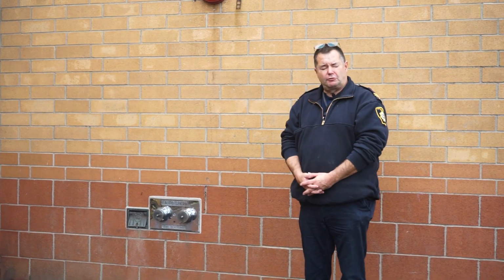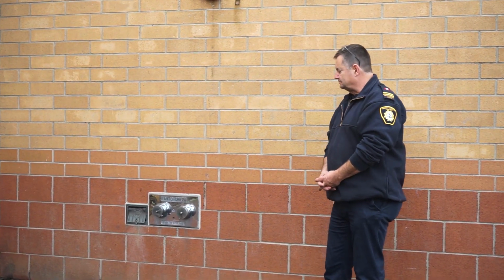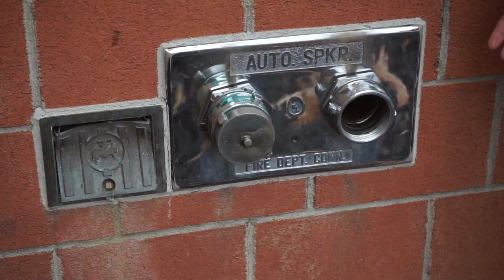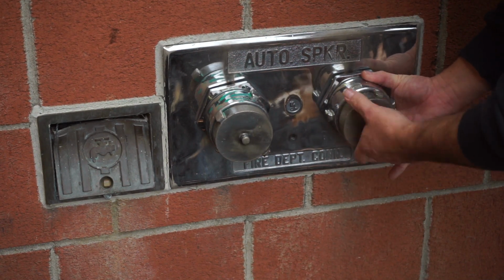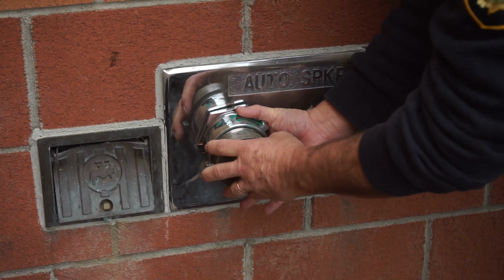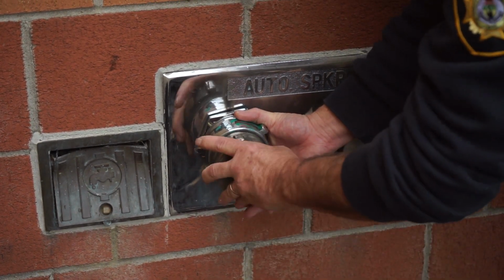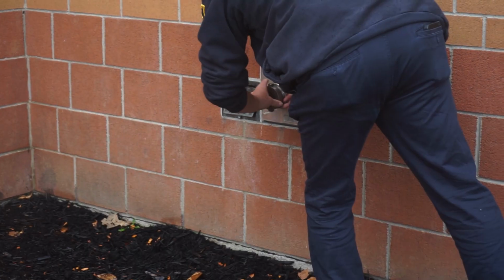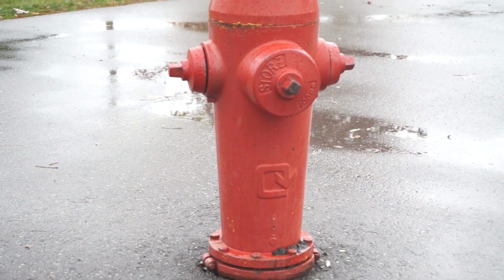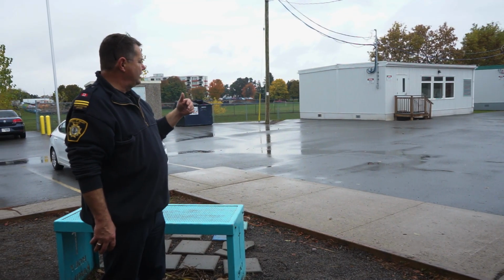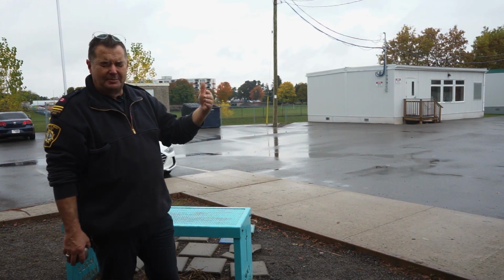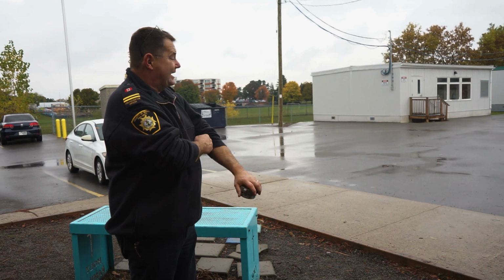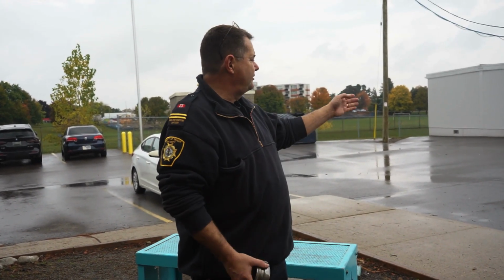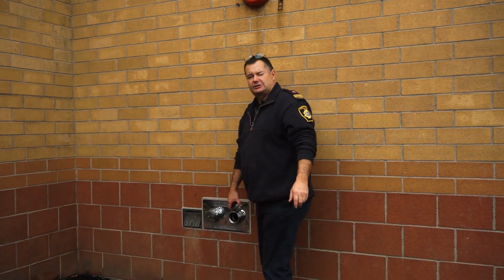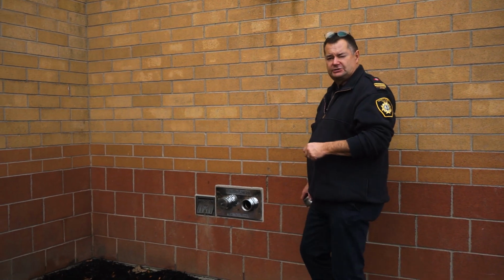In several buildings that are equipped with a sprinkler system, right here, this is what's called the fire department connection. It allows the fire department to attach to the building and assist the sprinkler system in extinguishing the fire. These are called fire department connections because the caps unscrew and the fire hose attaches straight to this, and the fire truck is allowed to pump water straight into the system. All fire department connections to a building are located within a specified distance away from a fire hydrant. Because this is an elementary school set in off the road, in the construction of this building they had to provide their own fire hydrant, hook their hoses to the automatic sprinkler system, and push water in to help the sprinkler system put out the fire.